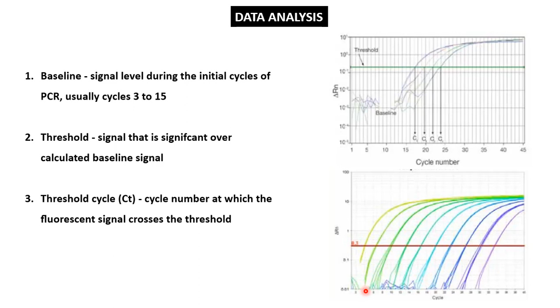Earlier in this video, I have shown this plot for calibration, and here I want to explain few more things from this plot. Remember, we should analyze this plot for the calibration, not for the sample. First is the correlation coefficient. Correlation coefficient tells how strong a relationship is between two variables. In this case, our sample data and the data from standard curve. Higher its value, better is the result. Y-intercept. The point on y-axis or CT value where a slope touches is the y-intercept.